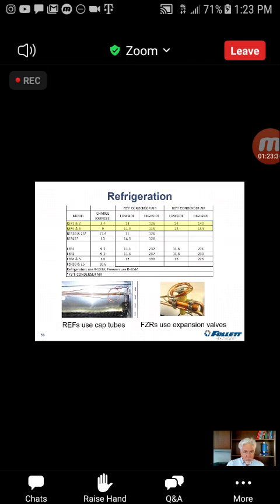So here they are, the Ref 1 and 2, and these are the charge sizes. Just one thing, this is actually coming up in the next slide. If you need to service the refrigeration system, these are sealed systems, mainly because of, number one, the very small charge size, number two, capillary tubes. These are critically charged units. So for initial access, you'll need piercing valves.